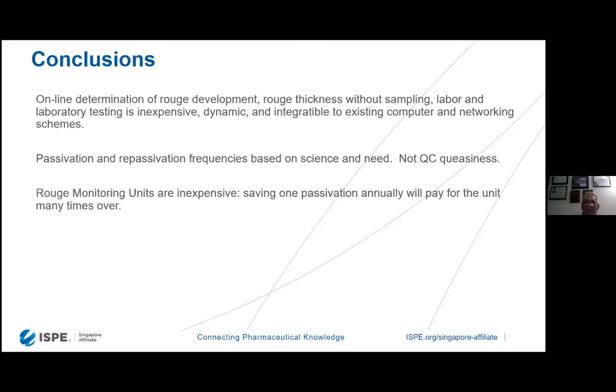Rouge monitoring units are inexpensive. Saving one passivation annually will pay for the unit many times over. These are not expensive instruments that you can integrate in order to show what you need to do. The cost savings can be tens of thousands to hundreds of thousands of dollars per year per site, easily. And depending upon what products you're manufacturing and how expensive those products are, think about now that if you don't have to go on downtime during Christmas shutdown in order to do derouging passivation for 4 days, and you can have the system running and producing product.